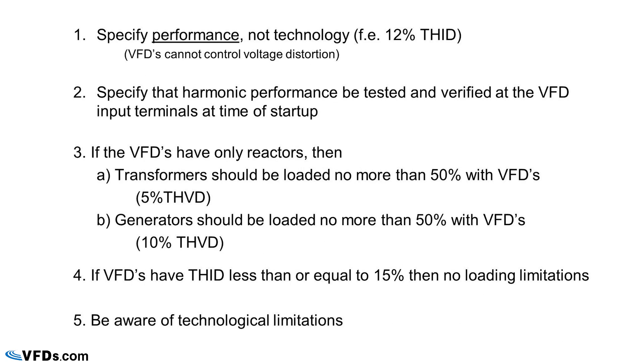So our solution: number one, specify performance, not technology. If you need 12% harmonic distortion, specify that. Next, specify that it be tested. In the case of variable frequency drives, we recommend that you specify that it be tested at the variable frequency drive input terminals. Next, if you have variable frequency drives with only reactors, don't load a transformer or a generator to more than 50%. If the variable frequency drives have other filters, go ahead and load that up to 100%. That's a brief overview of power system pollution and harmonics. If you'd like more detail, please feel free to call one of our knowledgeable specialists at VFDs.com. Check out our extensive inventory of drives and also of drive accessories, such as the three-phase line reactors that we have mentioned today.